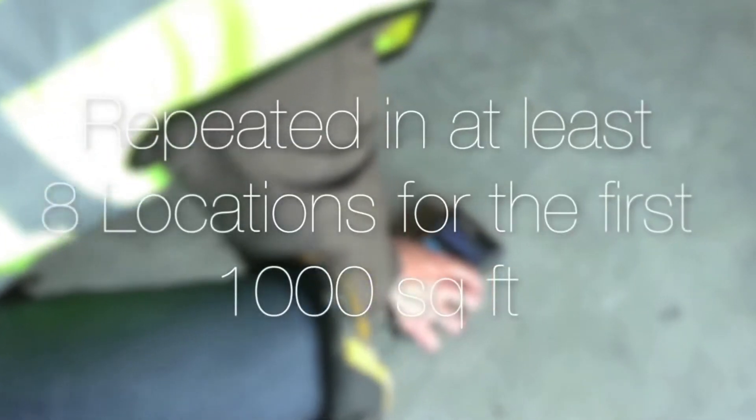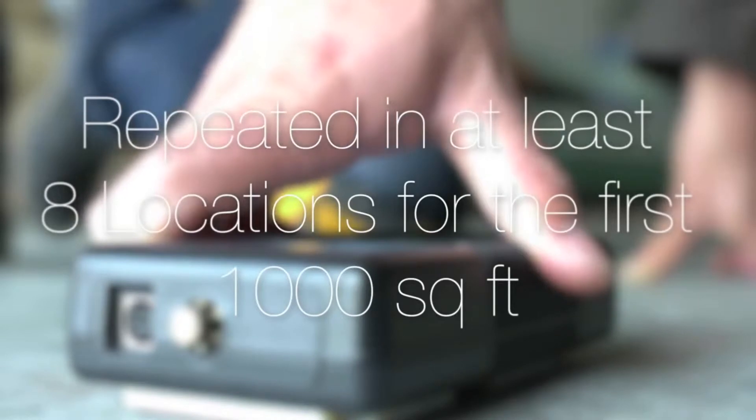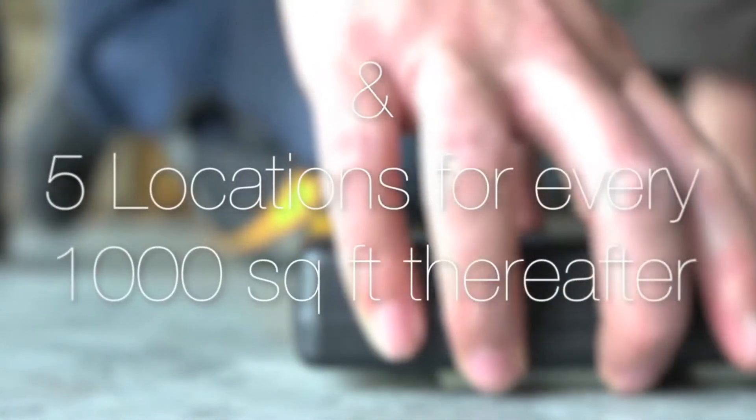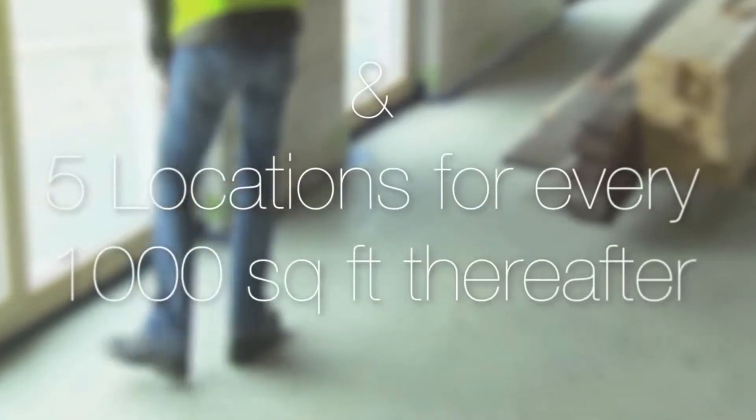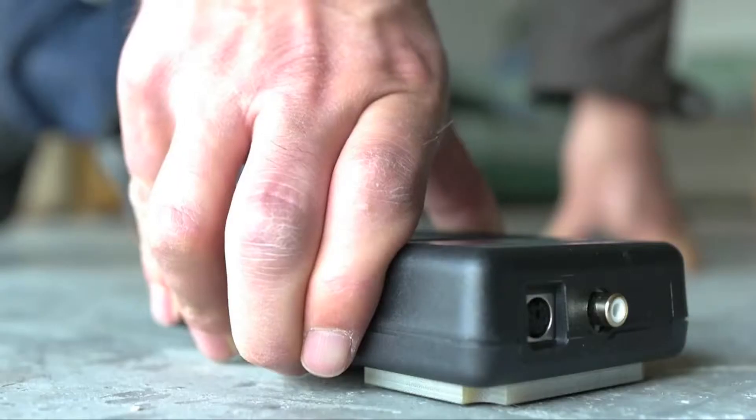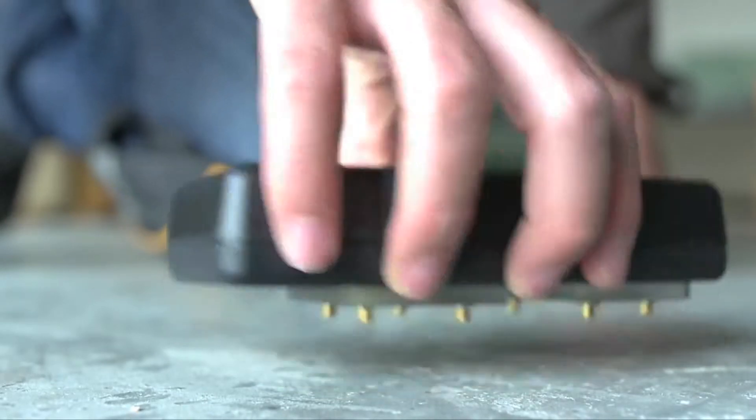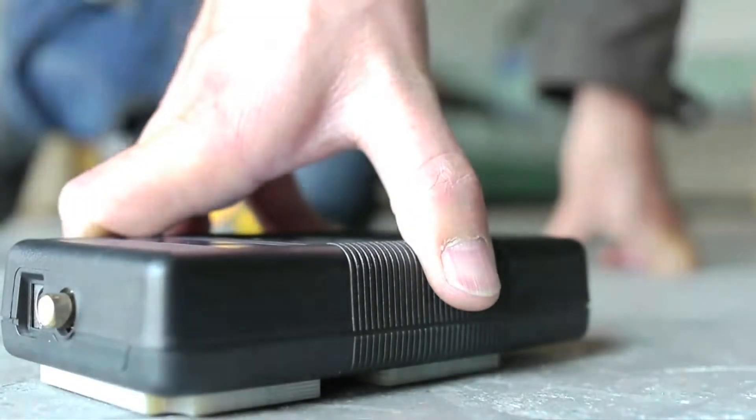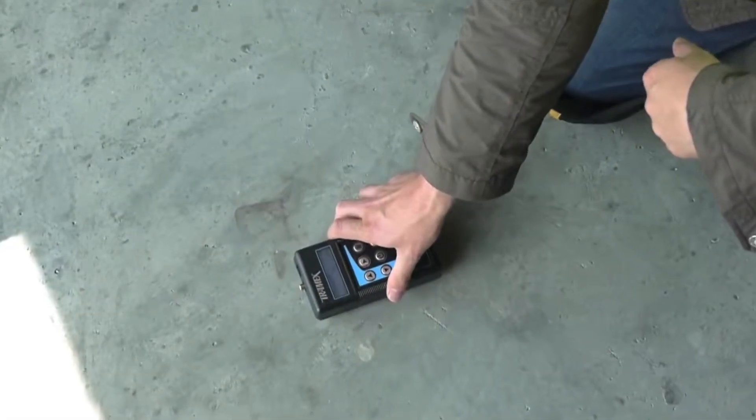This is repeated in at least eight locations for the first 1000 square feet and five for every 1000 square feet thereafter, allowing the user to build up a moisture map of the entire slab and identify when and where to test further, if testing for example to ASTM F2170.